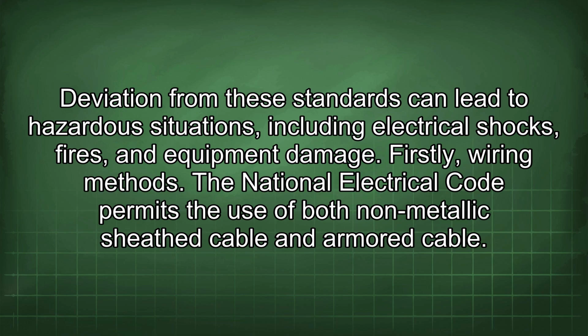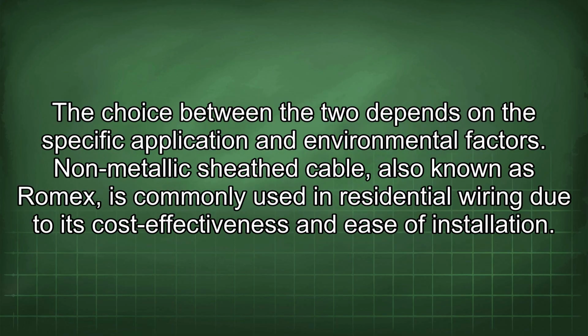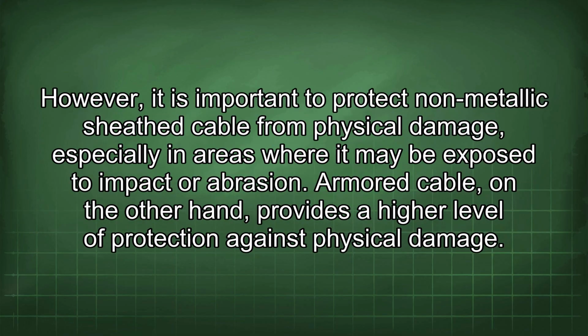Firstly, wiring methods. The National Electrical Code permits the use of both non-metallic sheathed cable and armored cable. The choice between the two depends on the specific application and environmental factors. Non-metallic sheathed cable, also known as Romex, is commonly used in residential wiring due to its cost-effectiveness and ease of installation. However, it is important to protect non-metallic sheathed cable from physical damage, especially in areas where it may be exposed to impact or abrasion.